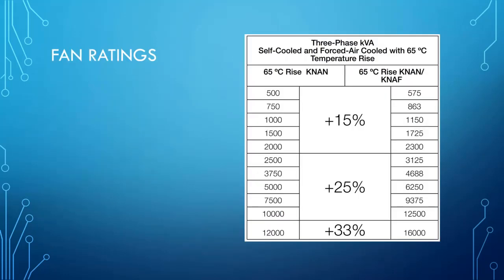Here is a chart that tells you what your kVA rating is when you put fans on the transformer. And you can see the percentage is not constant among all kVAs. Some of this is due to, as we discussed earlier, corrugated fins versus radiators and that kind of thing. So at 2000 kVA and below, you get an extra 15% of the base kVA rating by adding the fan package. At 2500 kVA and above, you get 25% of the base rating. And then at 12 MVA, you get 33%.